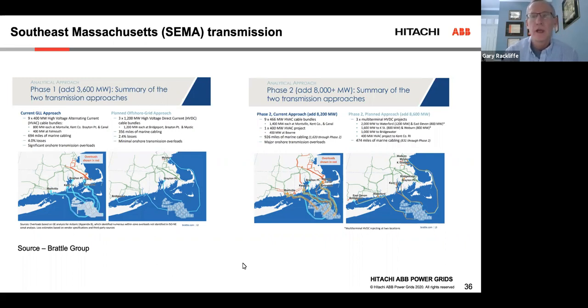And the picture on the right is showing phase two for that same wind farm development, adding another 8 gigawatts of power. Again, you can see more congestion associated with some of the AC cables. This was a study, I think published by the Brattle Group. It includes some other analysis by General Electric. There have been many studies looking at the congestion in Southeast Massachusetts, but the type of technology you use does matter. And this points to the need for overall system planning and coordination to make sure that the integration of this offshore wind is addressed, and that the onshore grid can handle that without creating additional problems.